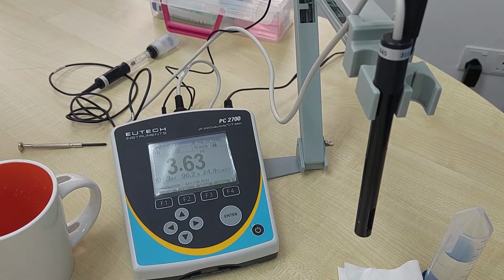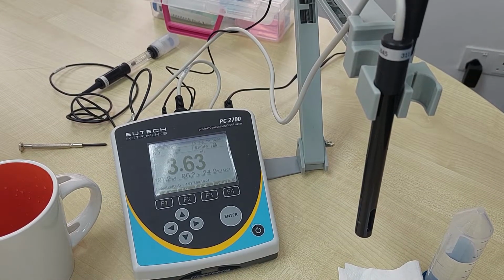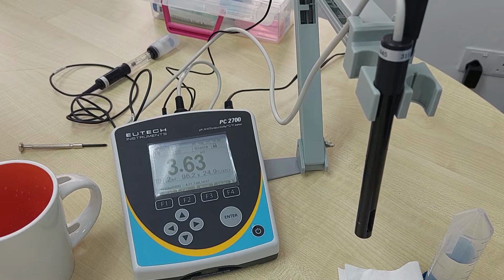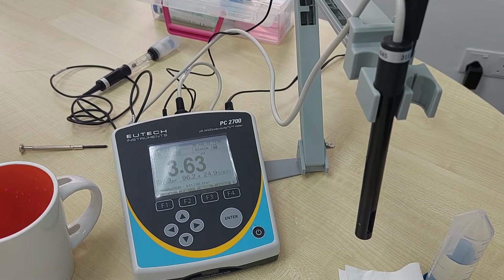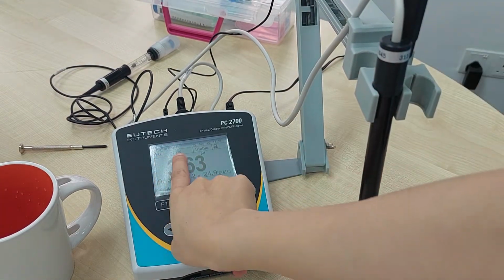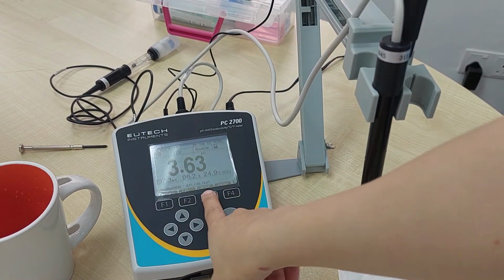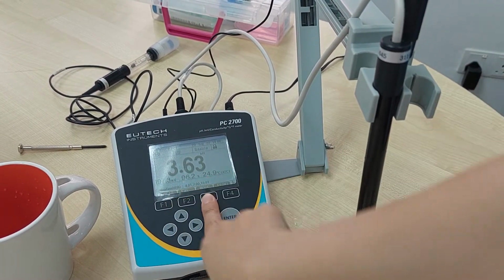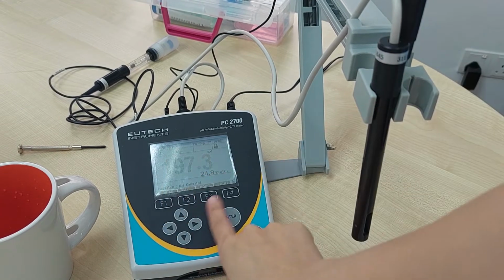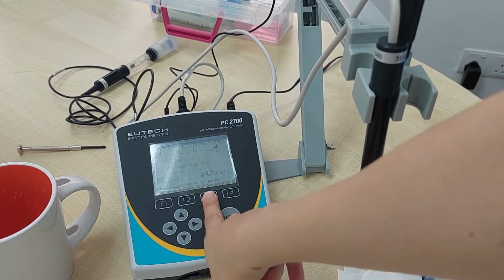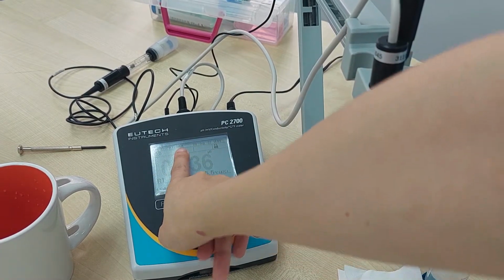Just now we have already done the pH calibration. Now we will go to the conductivity calibration. Okay, so to go to conductivity, now it's pH mode. So we just need to press mode right here, F3, and then you will change to millivolt. Then you press again, ion, press again. Okay, then it will go to conductivity.